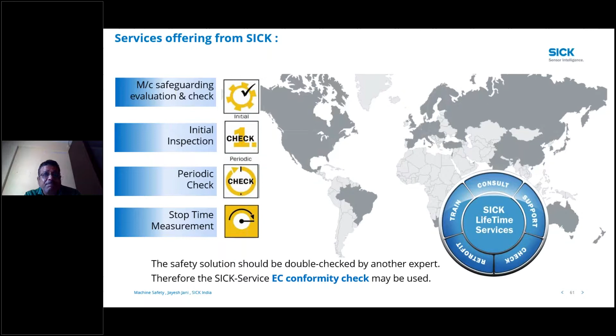So if your required safety distance is, for example, 400 millimeter from the press machine, and because of this mistake of calculation you install this light curtain at 200 millimeter, which is absolutely wrong, my machine will stop after chopping my hand, because we have already eaten the 200 millimeter with the reaction time of all this equipment, relays, contactors, PLCs, and machine and all. So there is always a dilemma at what distance we should place our light curtain, so that before our operator's hand reaches the cutting edge, all the energy has to be ceased. So the only variable is time, and it has to be derived perfectly.